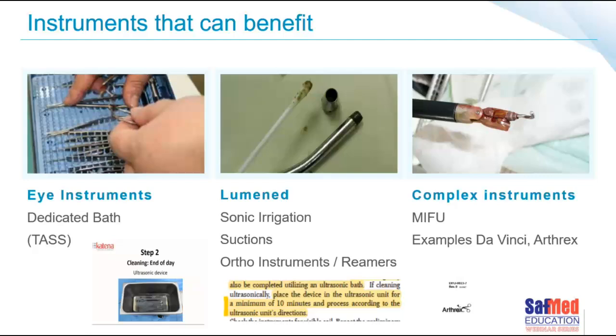If you read manufacturer's instructions for use, of which we should all have, you'll see, for example, perhaps some orthopedic devices. You'll see specific requests or instructions for use that stipulate that those types of devices should in fact be cleaned using ultrasonics. Complex devices like Da Vinci, maybe some Arthrex type devices, and based on manufacturer's instructions for use, will tell you which type of instrument or which type of device actually needs ultrasonic cleaning. Very important that we follow those manufacturer's instructions for use.